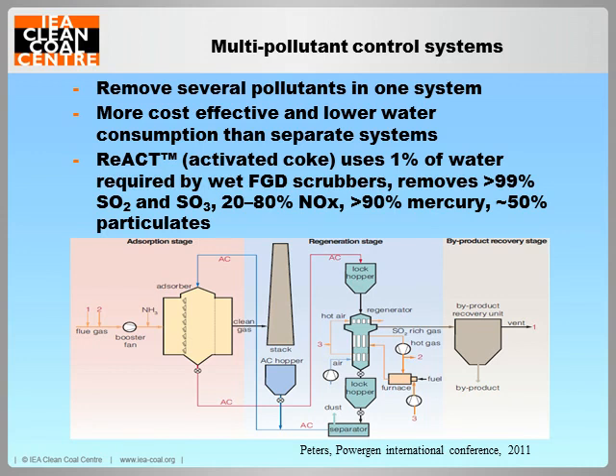One commercial system that is essentially dry is the REACT process. This uses only 1% of the water required by conventional wet FGD systems and also removes the pollutants which are listed on this slide. And this is actually when burning a low to medium sulphur coal. It's actually installed on a power plant in Japan.